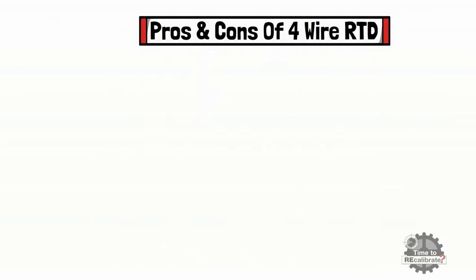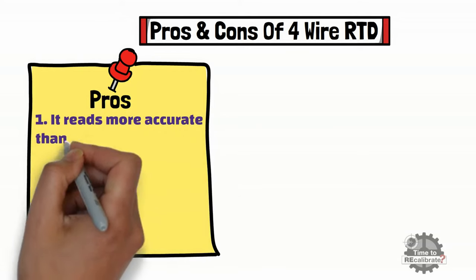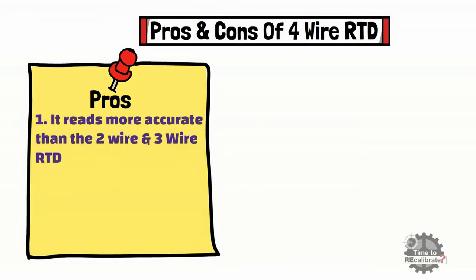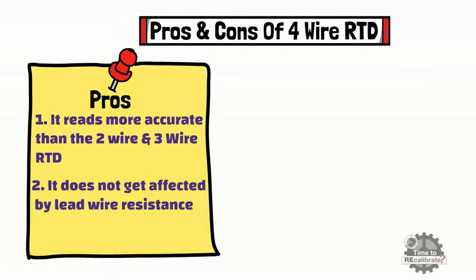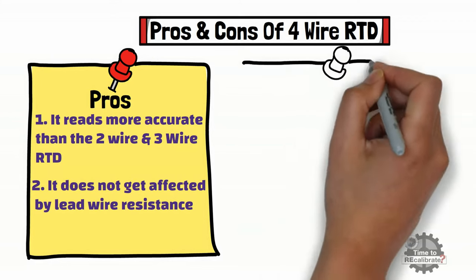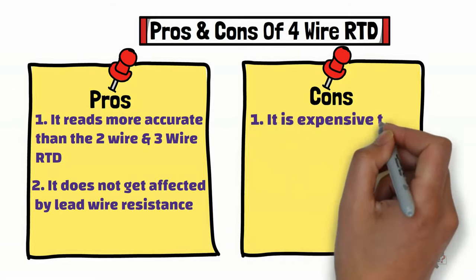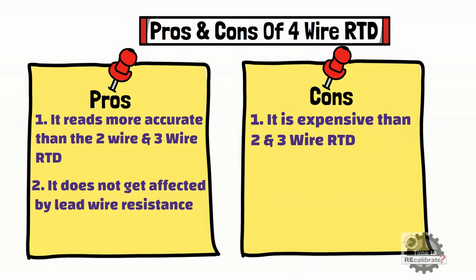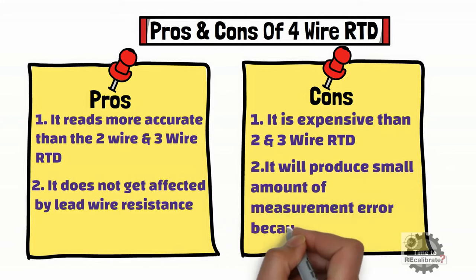Now let's learn the pros and cons of 4-wire RTD. For advantages: firstly, 4-wire RTD reads more accurately than 2-wire and 3-wire RTD, and it is commonly used in test laboratories where exact temperature readings are required. Secondly, 4-wire RTD does not get affected by lead wire resistance, and this is the reason it gives a high degree of accurate temperature measurement. There are a few drawbacks: first, 4-wire RTD is more expensive than 2-wire and 3-wire RTD. In addition, if you use a 4-wire RTD for a long period of time, it will produce a small amount of measurement error due to self-heating.